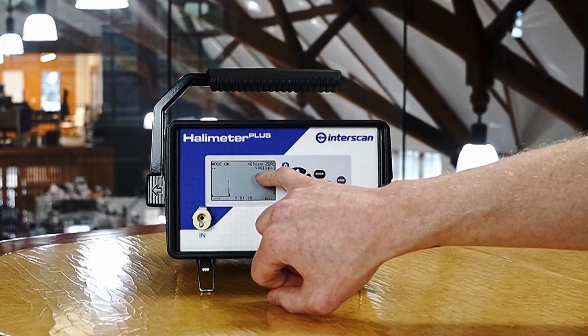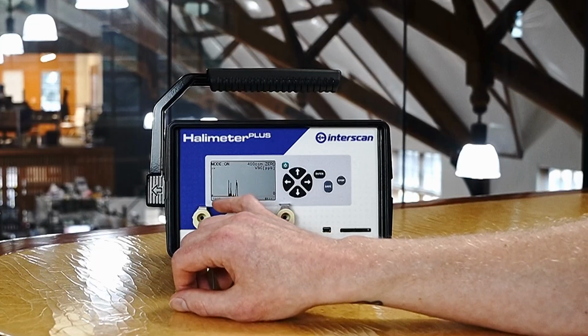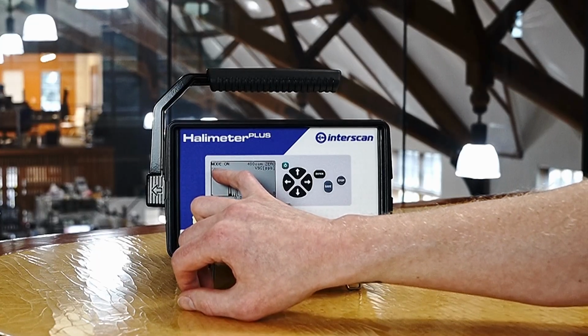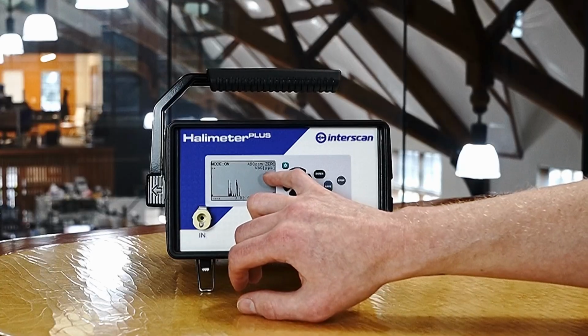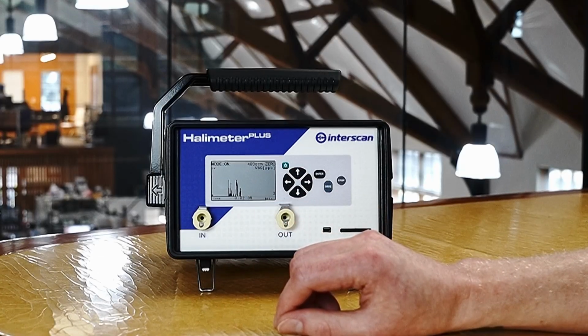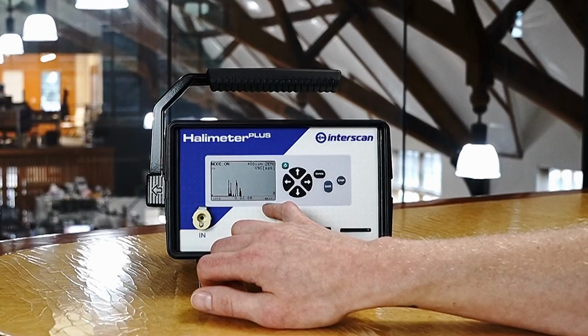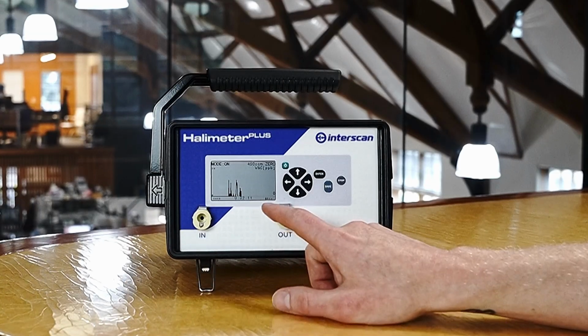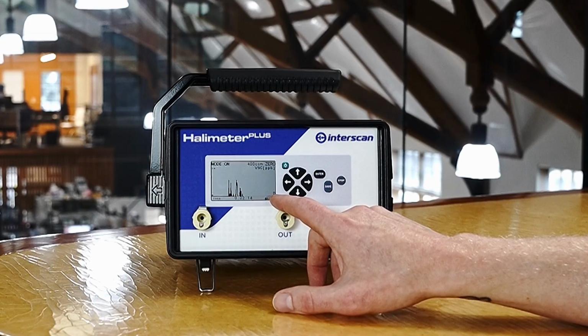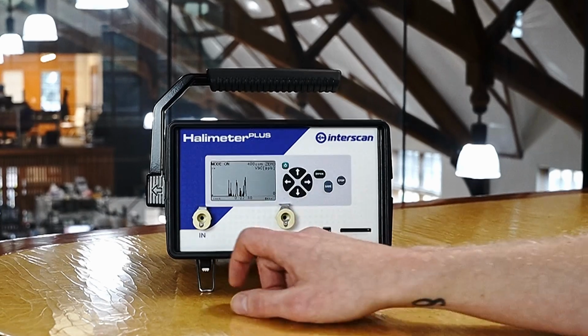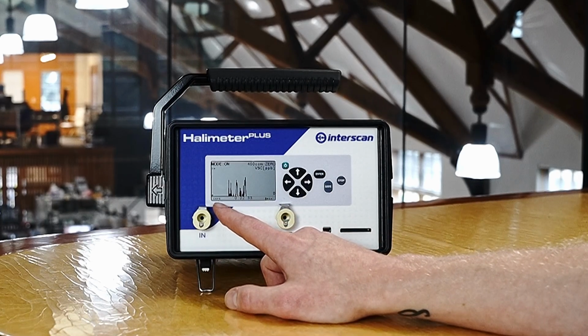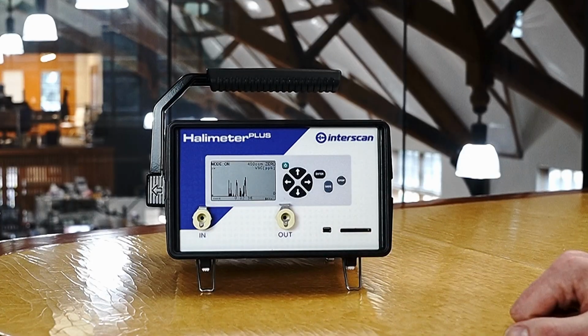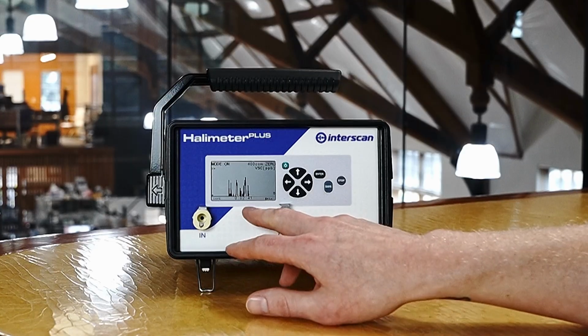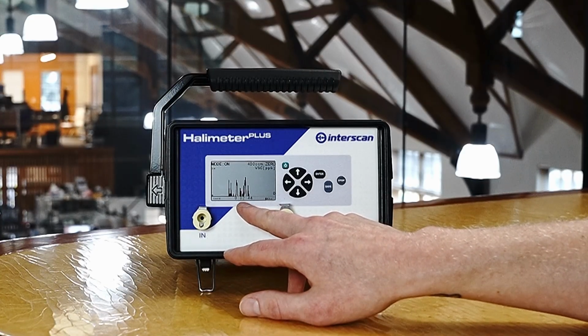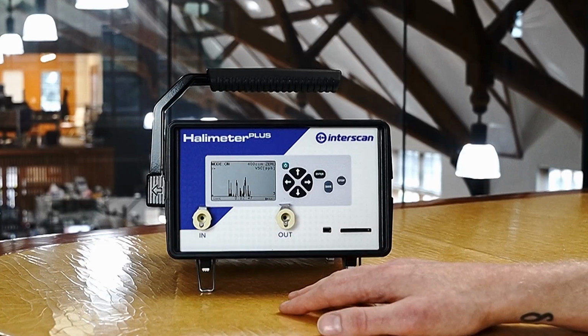In the top right, you also have your gas type. In this graph, you can see a range from 0 to 20, which would be 0 to 20 ppb in this case, based on your indicated value. In the bottom right, you can see your current battery level. Just above it is your current live measurement. In the bottom left, you can see a field that says save, indicating that your SD card is currently saving the data you're seeing. At the very bottom of the screen, in the middle, you can see the current timer that tells you how long you've been logging data.